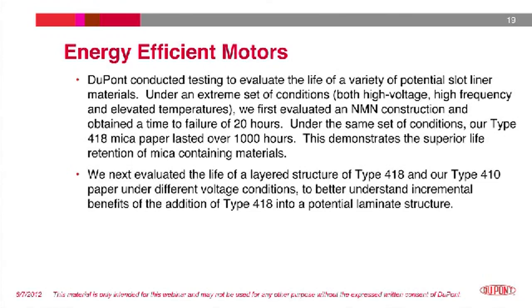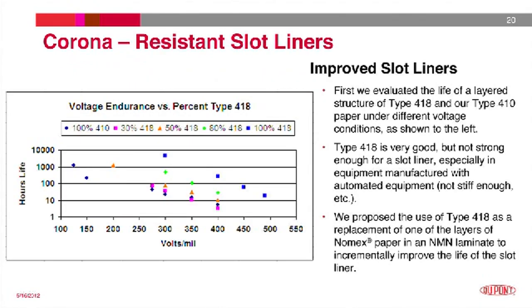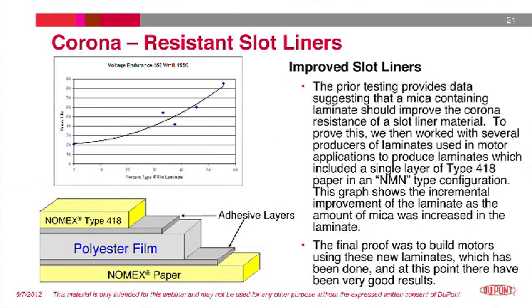We next evaluated the life of a layered structure of Type 418 and our Type 410 paper under different voltage conditions to better understand incremental benefits of the addition of Type 418 into a potential laminate structure. This chart shows the results of the testing of layers of Type 410 and Type 418. Type 418 has very good voltage endurance, however, it is weak mechanically. So, to help provide an optimized solution, we proposed an NMN laminate where one of the two layers of Nomex paper would be replaced by Type 418 to incrementally improve the corona resistance of the slot liner to help improve the life of the motor. This testing proved that by substituting portions of the laminate with Type 418 papers, we could improve the life of the laminate versus that of typical NMN laminates.